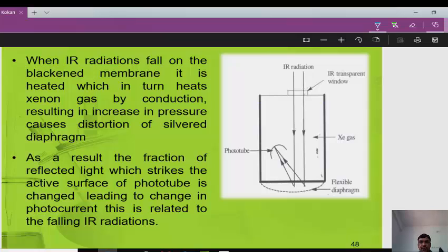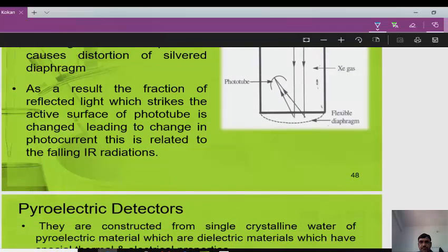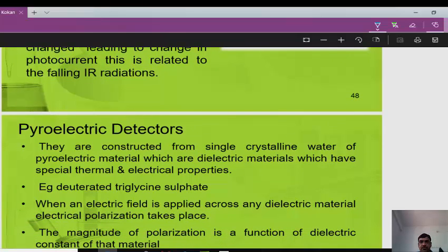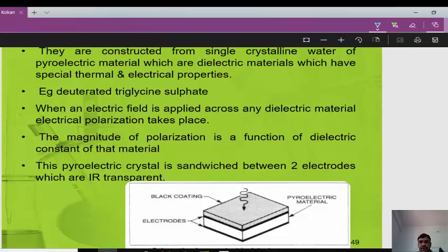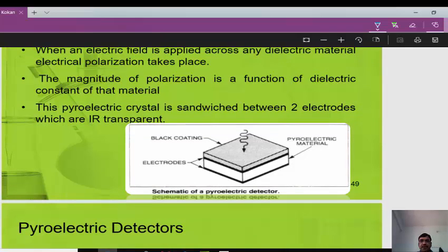The Golay cell is a sensitive gas thermometer. Xenon gas is contained in a small chamber; one side has a flexible membrane. When IR radiation falls on the blackened membrane, it heats the xenon gas, causing the membrane to flex. A beam of light reflected from the silver surface to a photoelectric cell changes as the membrane moves, leading to a change in photocurrent proportional to the IR radiation.